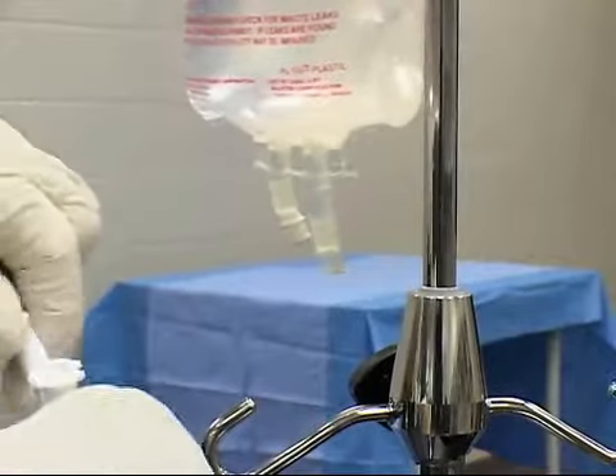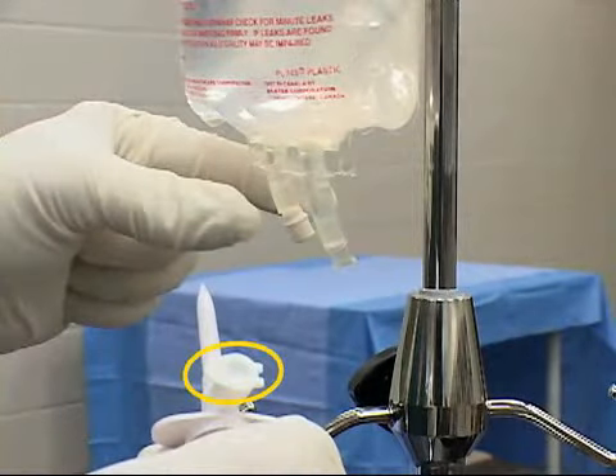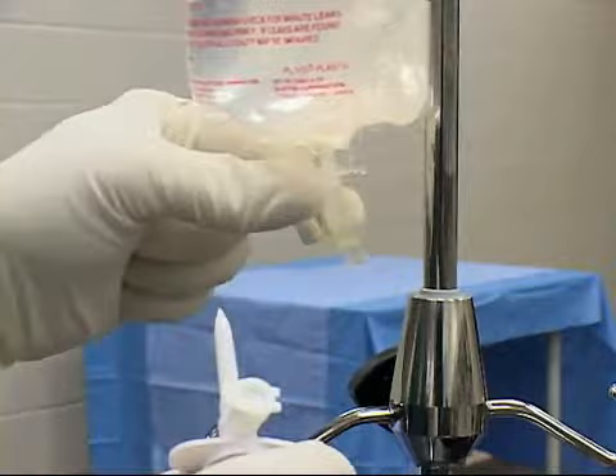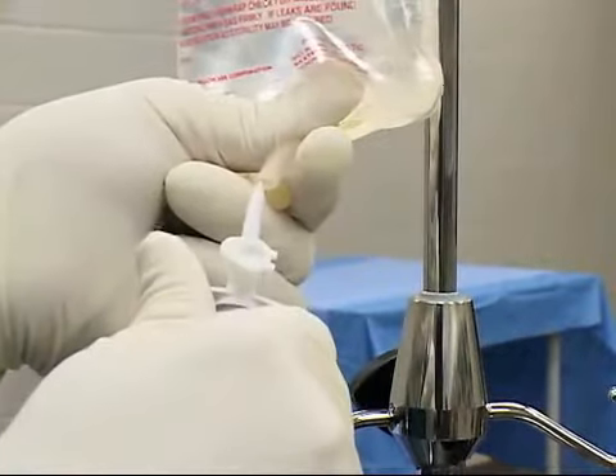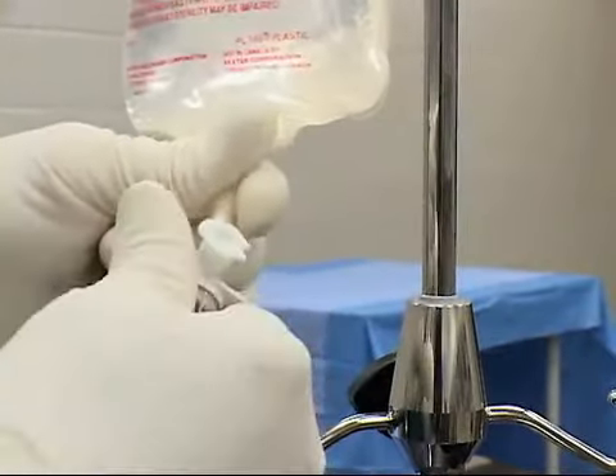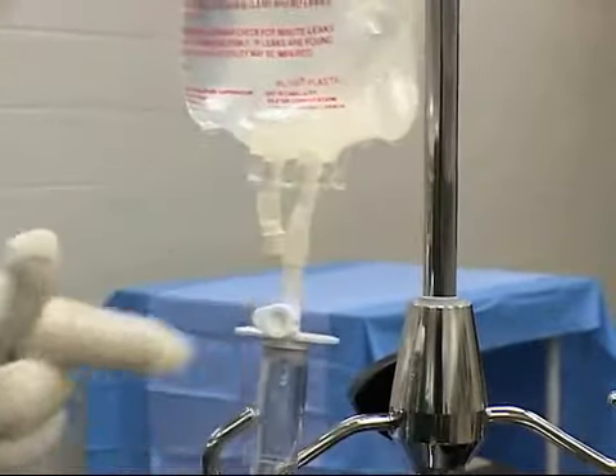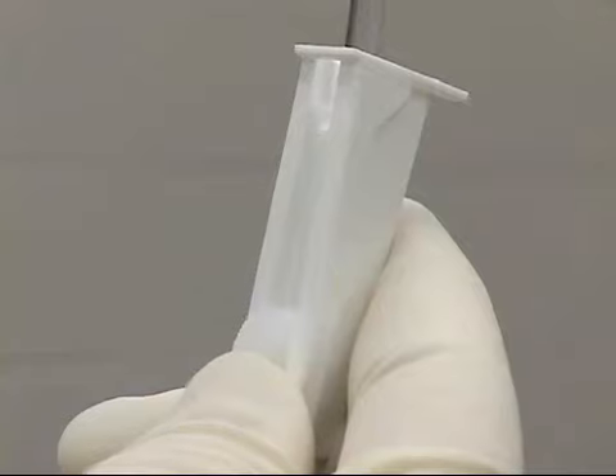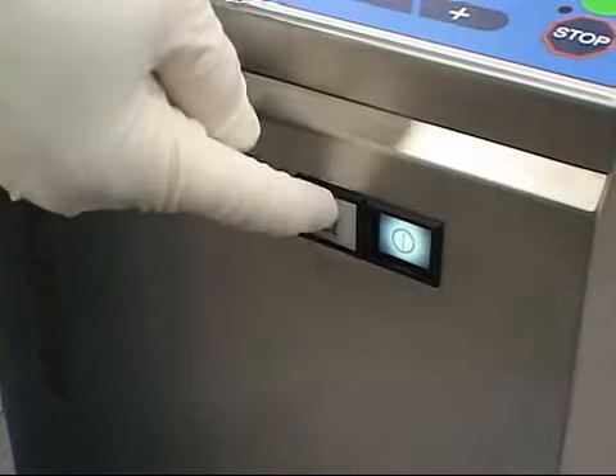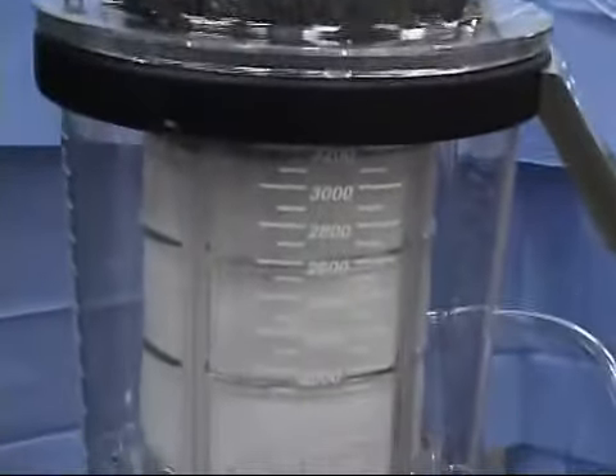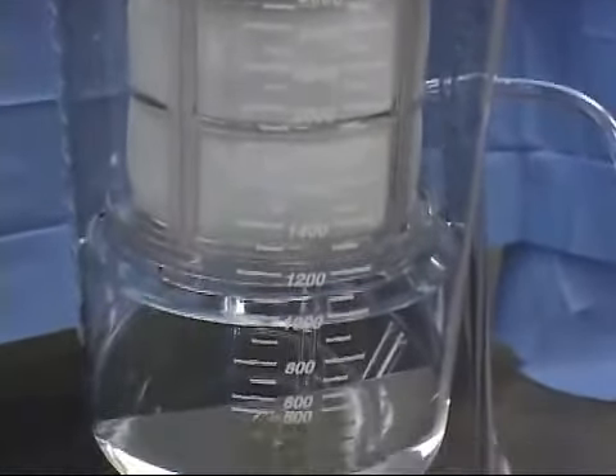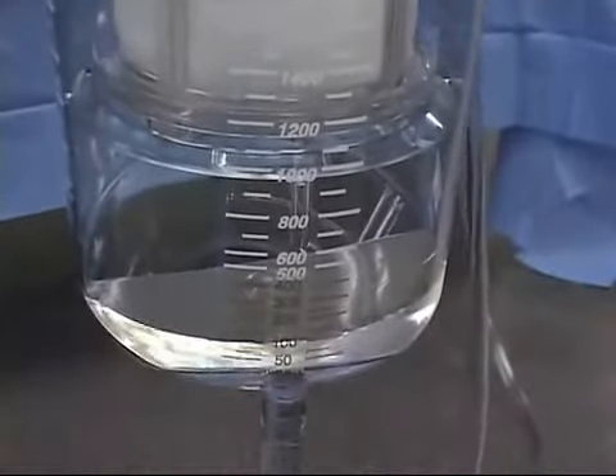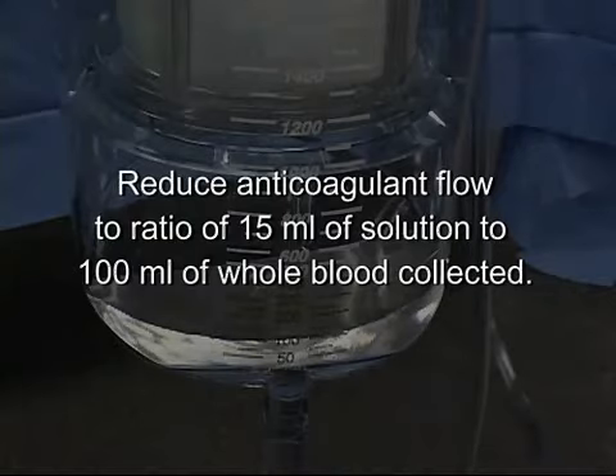If the anticoagulant container is non-vented, open the vent cover on the drip chamber. Next, spike the anticoagulant solution. Then, open the roller clamp on the anticoagulant line. Turn on the vacuum as shown. Prime the reservoir with approximately 150 to 200 milliliters of anticoagulant. Reduce anticoagulant flow to a ratio of approximately 15 milliliters of solution to 100 milliliters of whole blood collected.